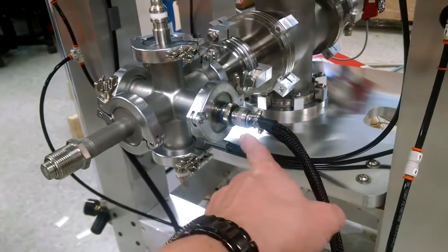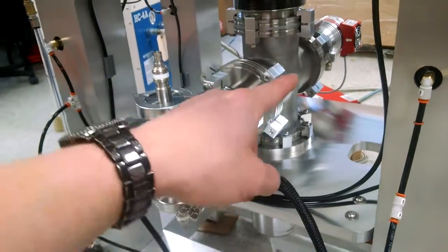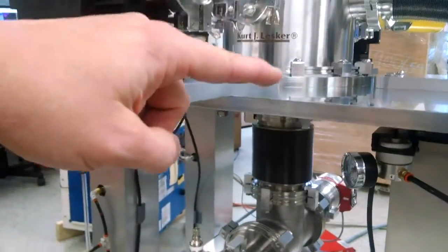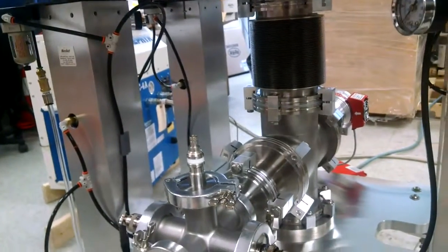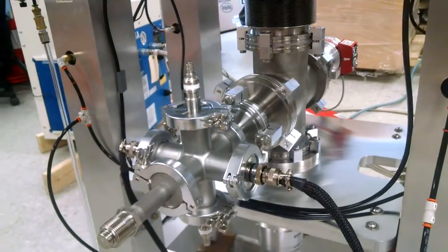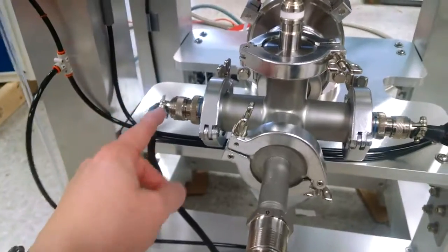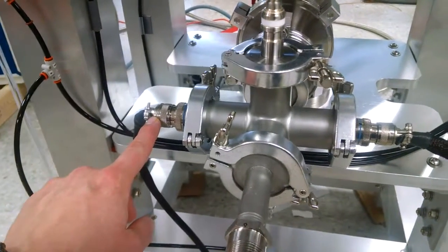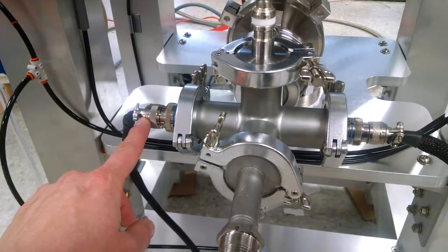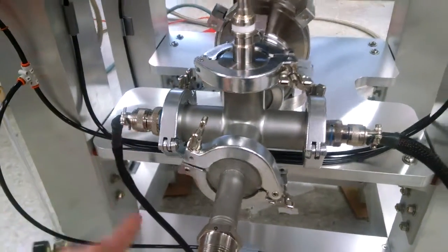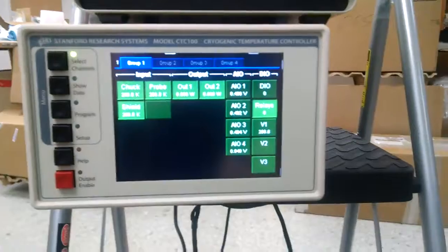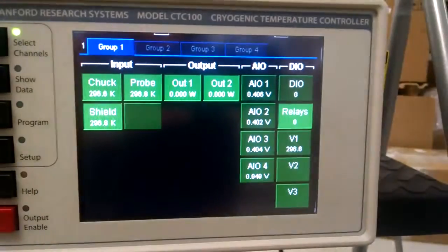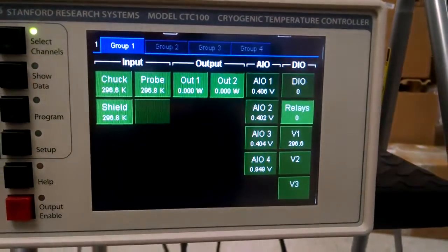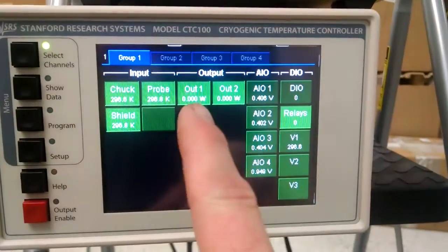These are heater connections. So there are 4 heaters throughout the system. So once you cool it down to cryogenic temperatures, you can heat it back up. We have 3 silicon diode temperature sensors that are good down to 4K and below. Very accurate. We're reading those with the Stanford Research Systems cryogenic monitor.